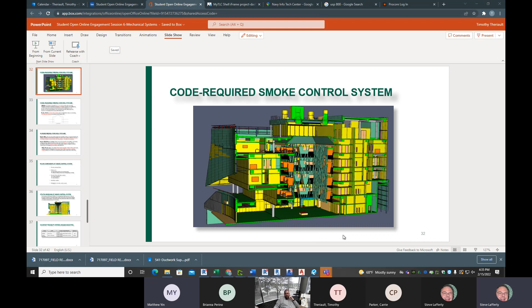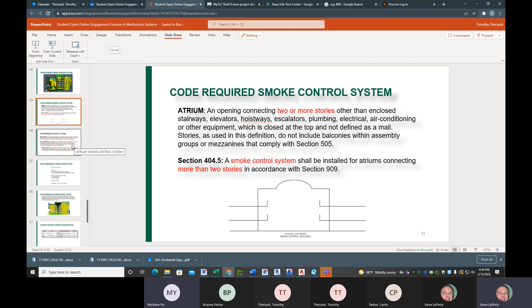If you look at the next slide, this is basically the language from the building code. Let's say IBC, even though in Florida they adopted the Florida Building Code, but the language should be the same. An atrium is an opening connecting 2 or more stories in any building, but not all atriums need a smoke control system. Only atriums connecting more than 2 stories, meaning 3 stories or more, will require a smoke control system designed in accordance with building code section 909, which is the section that regulates all the requirements regarding smoke control systems.